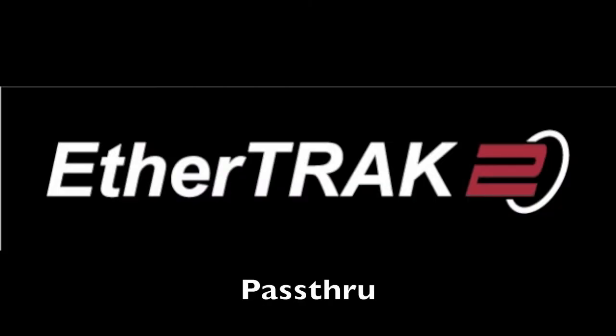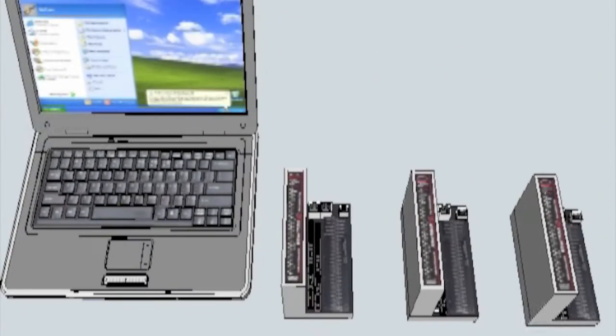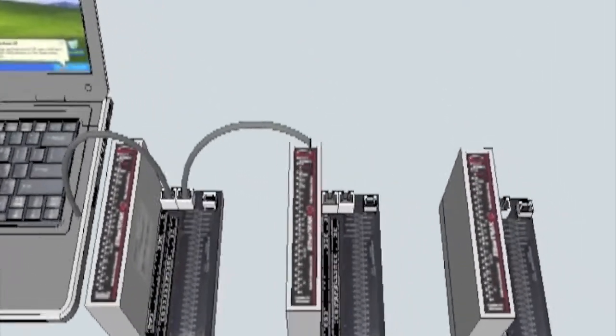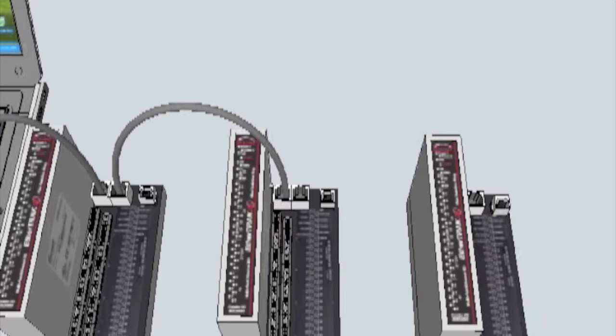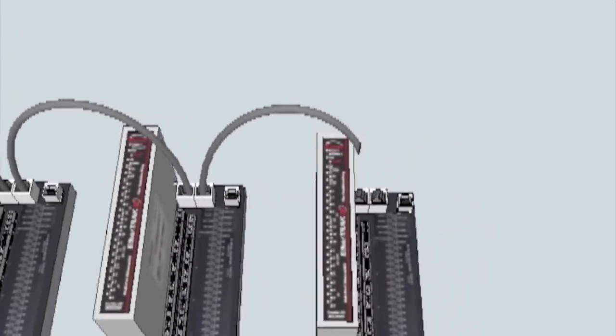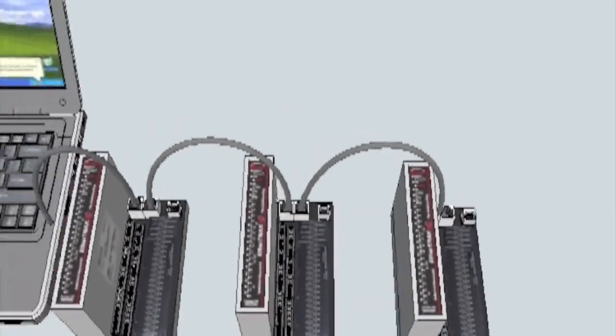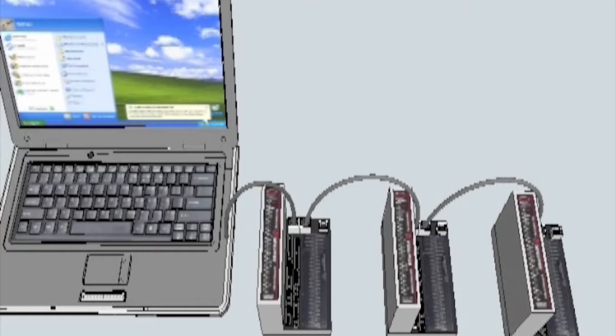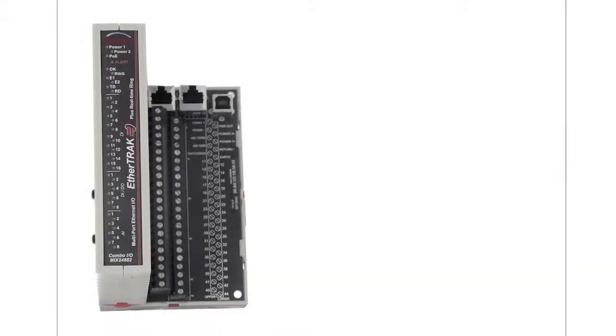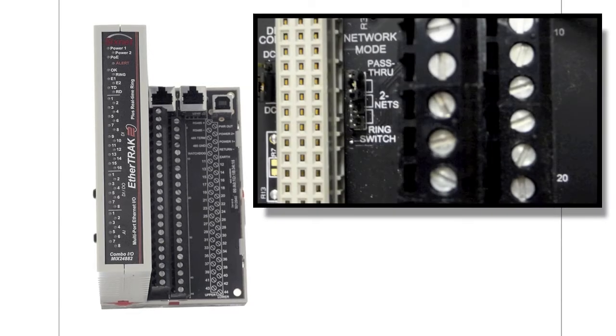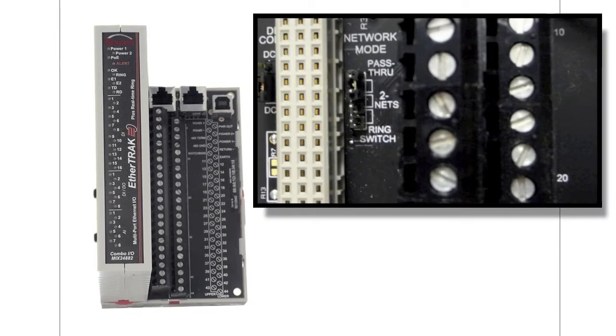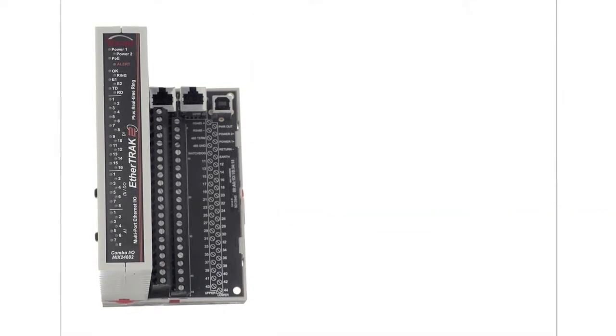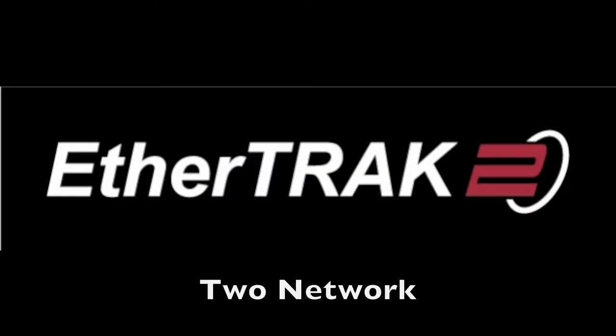The second option is the pass-through configuration or switch elimination mode. In this configuration, no additional switch is required, making it the perfect option where pricing and space constraints are paramount. The pass-through option uses the two Ethernet ports on the EtherTRAK 2 as a simple 10-100 unmanaged switch. To configure this option, simply unplug the logic module from the base and change the network jumper to the pass-through position.